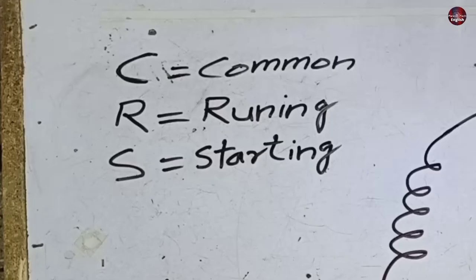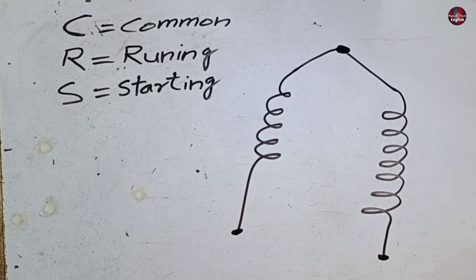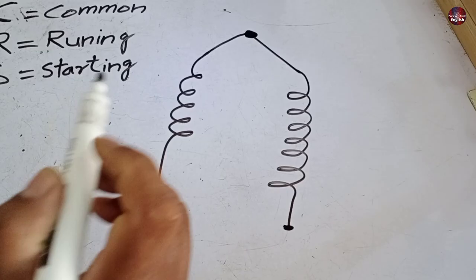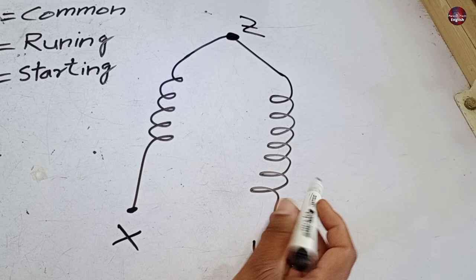I have written CRS here, which is common, starting, and running. If I directly write the CRS on the coils, it will make no sense as I don't know which coil is common, run, and start. So I will randomly write X, Y, and Z on the coils to find out CRS. Now I will make pairs of these X, Y, and Z. Three pairs will be made: the first pair is X and Y, the second is Y and Z, the third is X and Z.